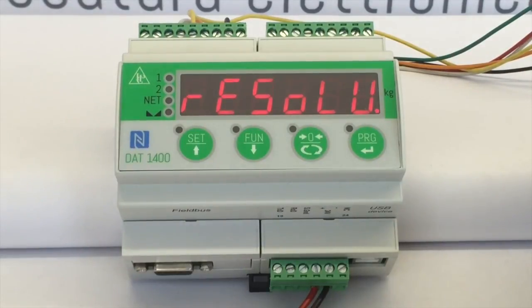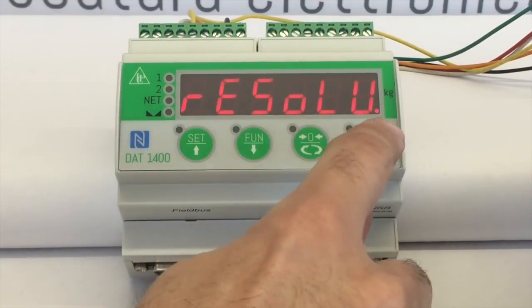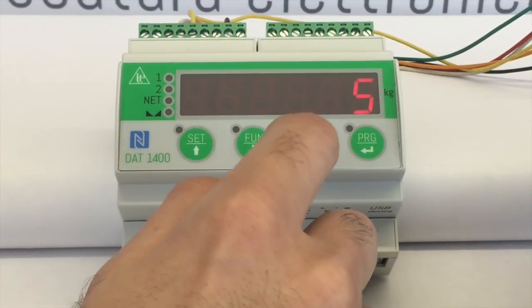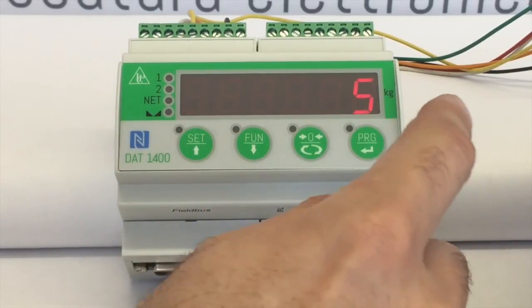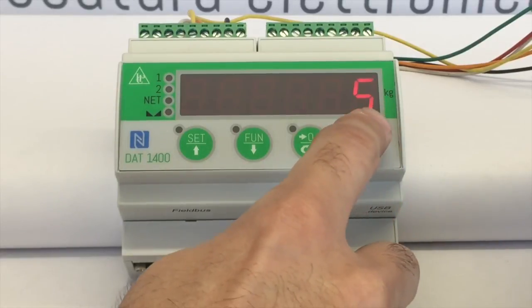In the RESOLUTION submenu you can set the minimum division of the instrument using SET and FUN buttons. Let's set 5 kg. Press and hold PRG for 2 seconds to confirm.